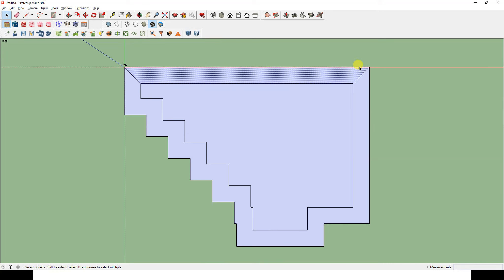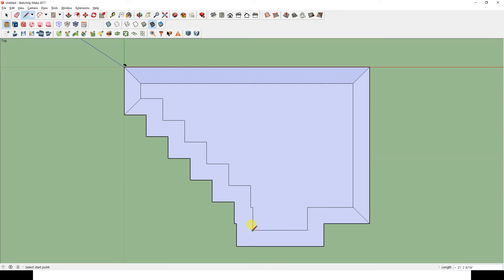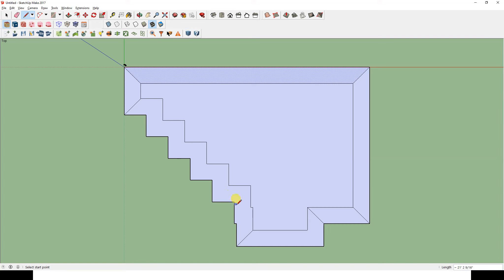A simple way in SketchUp is the offset tool. You can just click the edge, type in 15 feet and hit Enter, and that makes a line inset 15 feet. In making a simple core and perimeter model, I recommend cutting all the corners so that each thermal zone that looks a certain orientation only has a wall that faces that orientation. For instance, if we draw these little corners, this space now only has one exterior wall — it doesn't have any of the adjacent wall — and it can be defined as our north zone very easily.